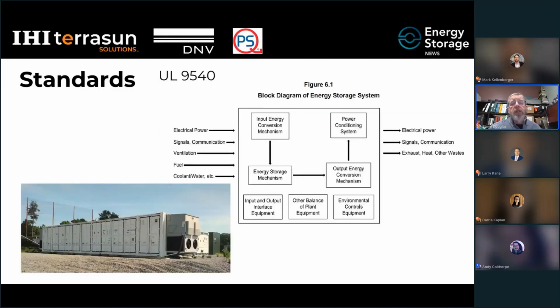In UL 9540, as part of the scope, it refers to Figure 6.1, which shows what is an energy storage system and what it comprises. The confusing part, given how the scope is written in the current standard, is that one might conclude the energy storage system needs to include everything inside that box. But looking at the picture on the left, there's a 5 megawatt hour energy storage system where the batteries and most of the controls and protection are inside that sea-container-looking enclosure, with air conditioning on the end, a conditioning unit or inverter behind it, and the transformer behind that.